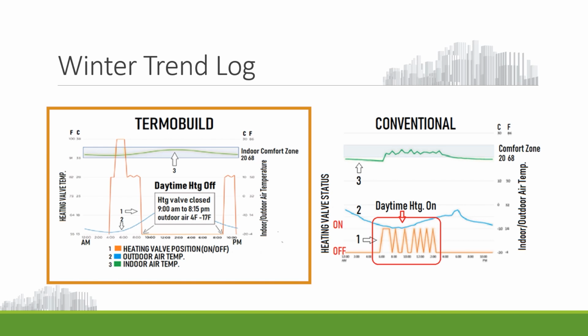If we look at the top portion of this left-hand graphic, you can see that even though the heating system did not come on during the day, the temperature drifted very slowly upward during the day. And the reason for that is the concrete hollow core slabs are absorbing the heat energy and the load from occupants of the building, the lighting system in the building, and other equipment that is in the building.